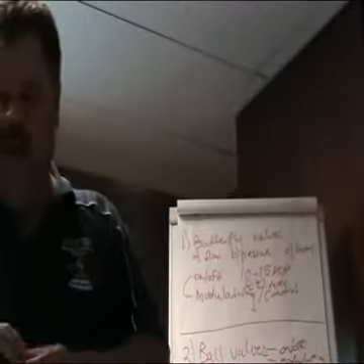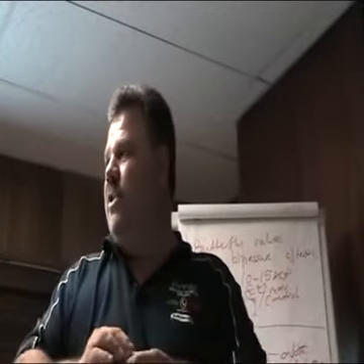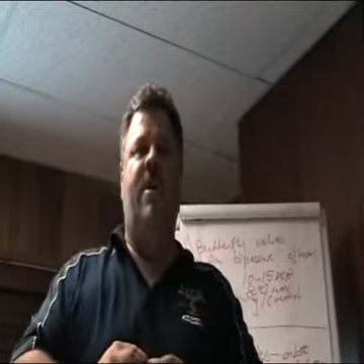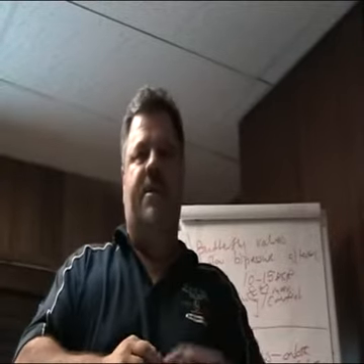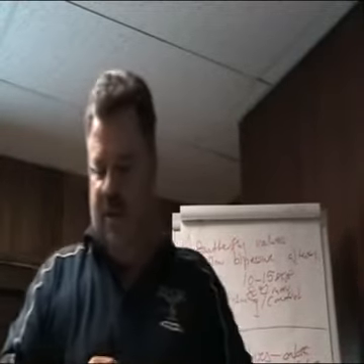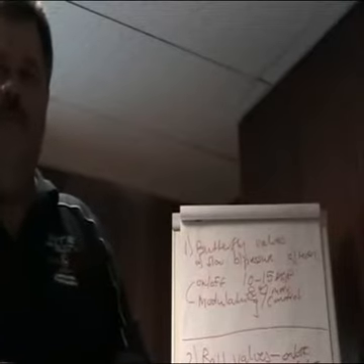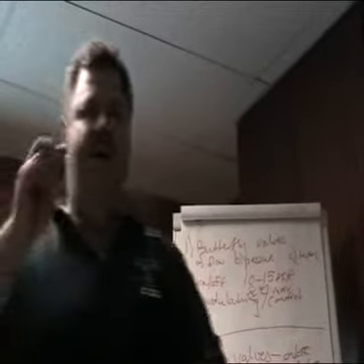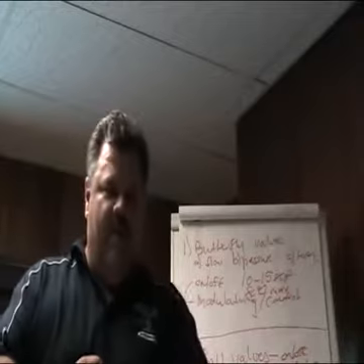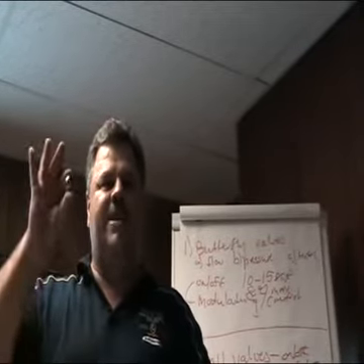Okay, so everybody understand a ball valve: 90 degrees, open and close, same sizes as what you can get on butterfly valves, also low pressures. And trunnion mounts, high pressures, high temperatures, but more expensive than butterfly valves. And they have the highest CVs in industry. Correct. Why, David? Thank you for that. Why does the ball valve have the highest CVs? Because it's a line size valve.